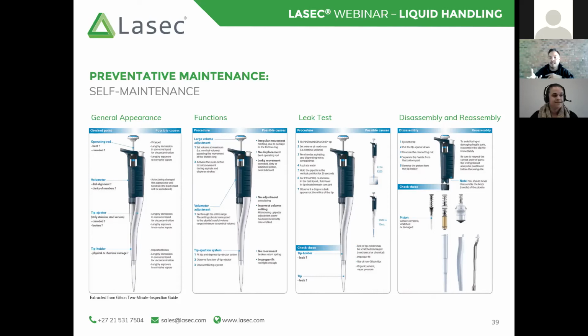The cost of replacing a piston for higher end pipettes can be almost 50%, if not more, of the cost of the pipette. So you really want to avoid corrosion of this piston. In such a case, I do recommend that you dismantle it, removing that sample from the tip holder, avoiding any sort of further corrosion down the line. And in dismantling the pipette, you are not necessarily going to affect the calibration of that pipette. Importantly, only provided that you replace it with exactly the same parts that you took apart, okay?